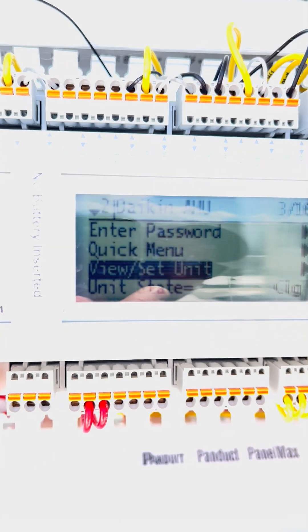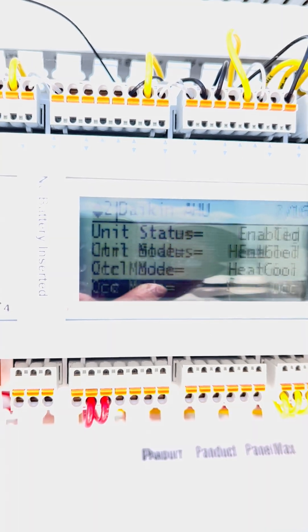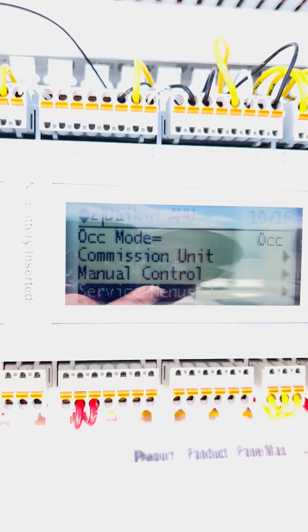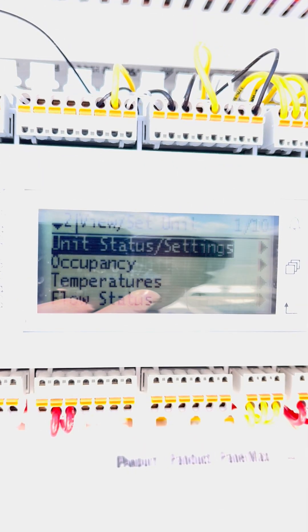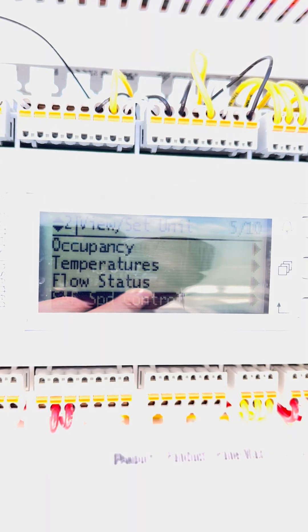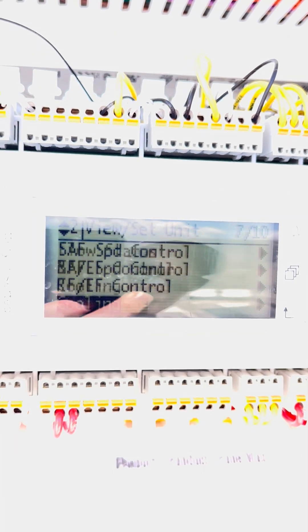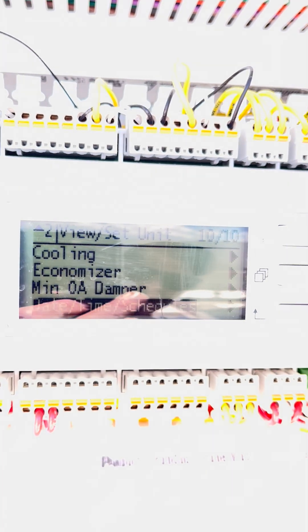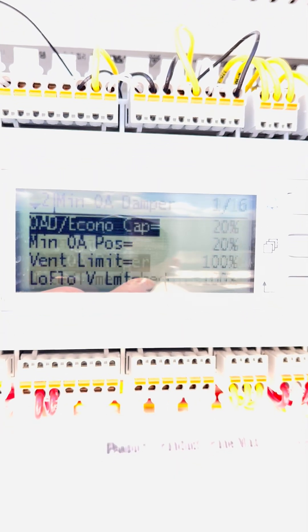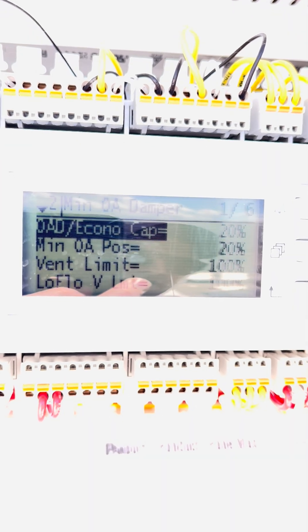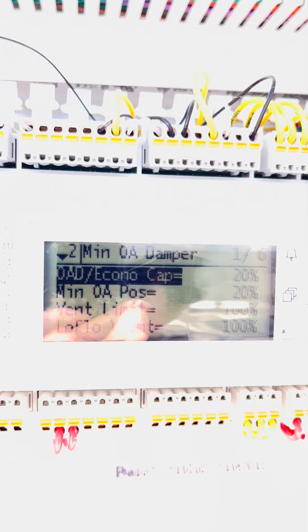So now what we're going to do is we're going to go in and we're going to go down to a few things. First, we're going to go to unit view set. We're going to go down to outdoor, min outdoor air damper position. In the min outdoor air damper position, you're going to see here that OAD capacity. This is what it's currently calling for, 20%.